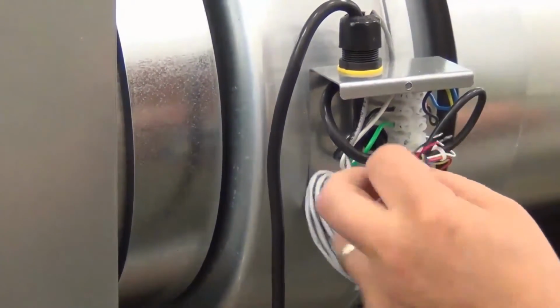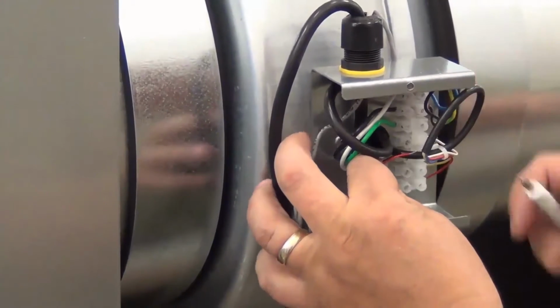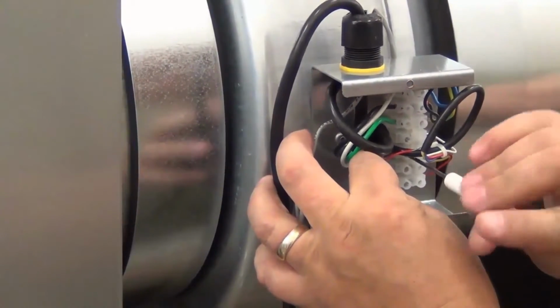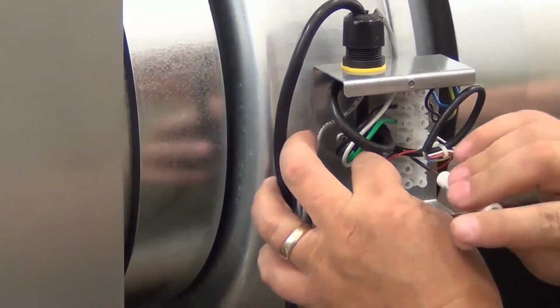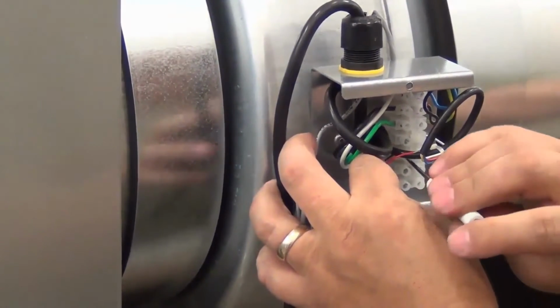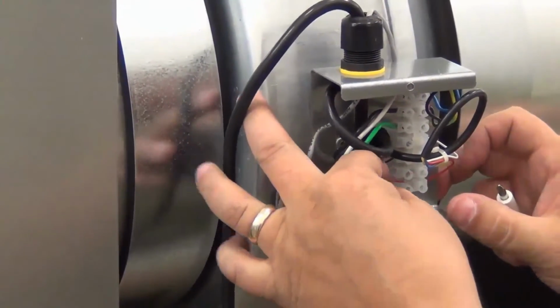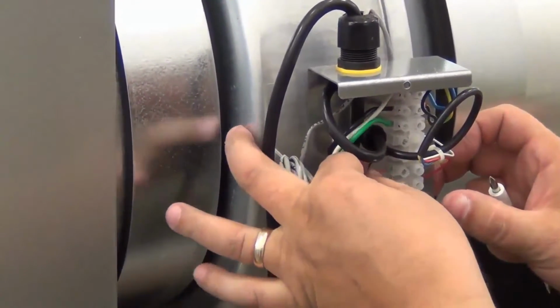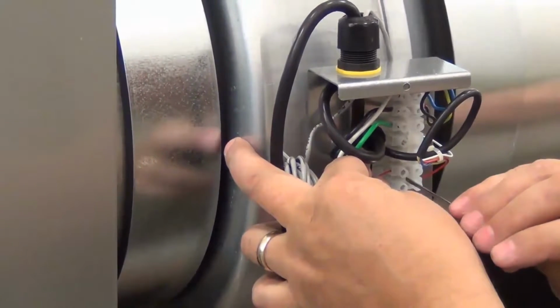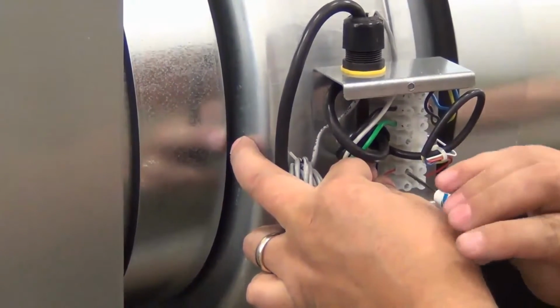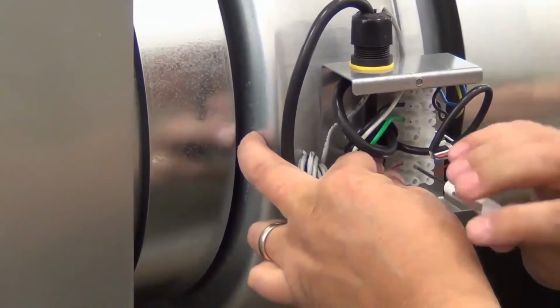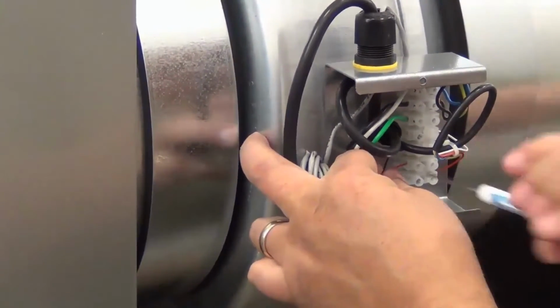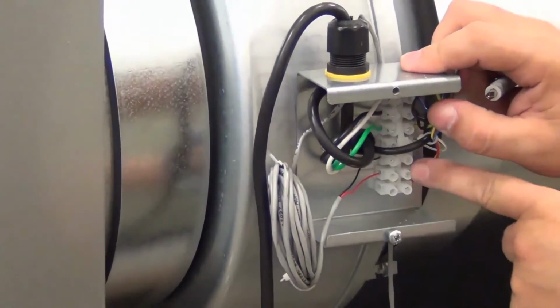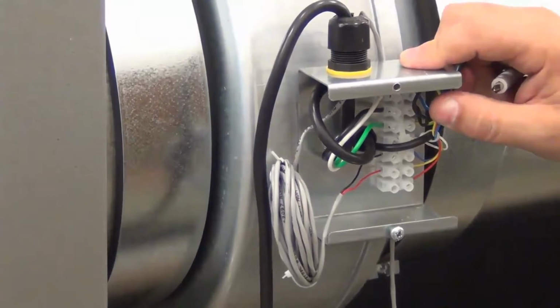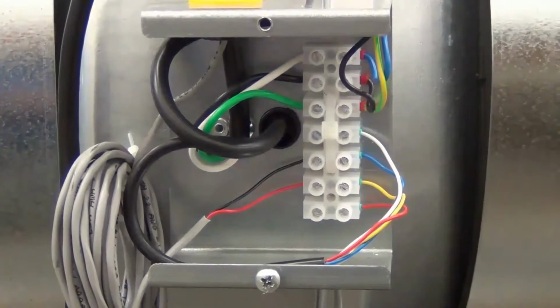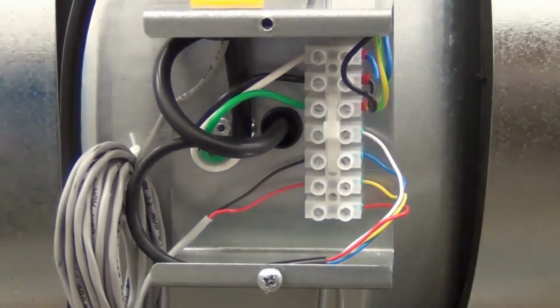Connect the low voltage DC wire from the controller. Note, these wires are polarity sensitive. Your positive 0 to 10 volt goes to your signal wire, which in this case is the yellow on the connector block, and your negative goes to the blue wire on the connector block. Although your wire colors may be different, the connection should be made like this.